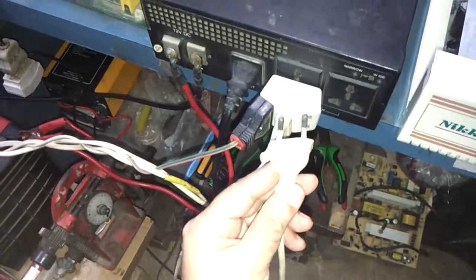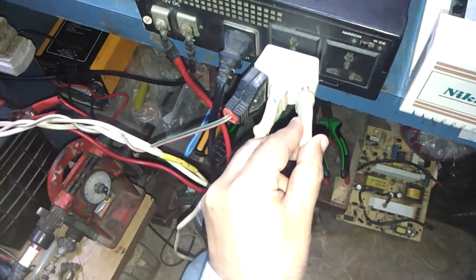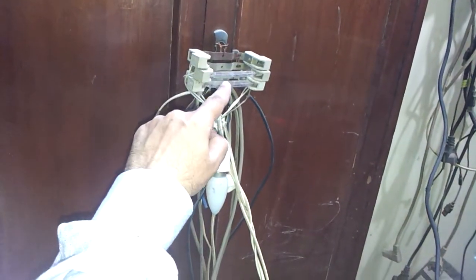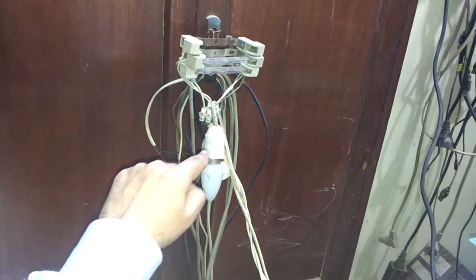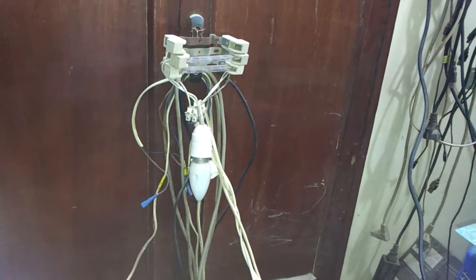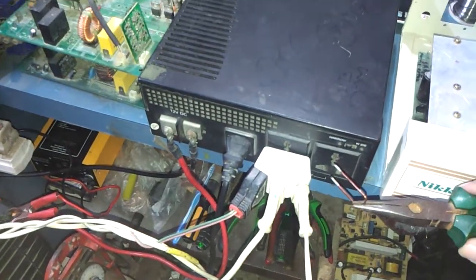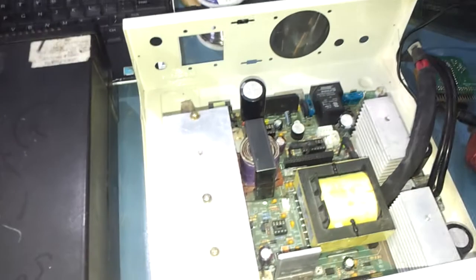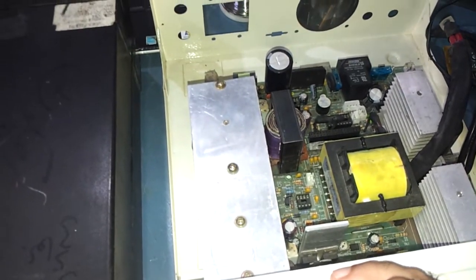Now let us cross limits. Before this demonstration, the overload trim pot was intentionally set by me beyond specifications for overloading of about 960 watts of real load. So this output short circuit shall exceed limits with the addition of one more halogen lamp.